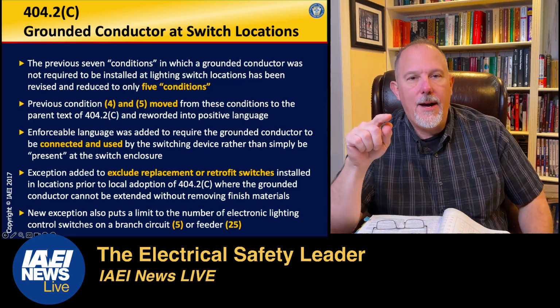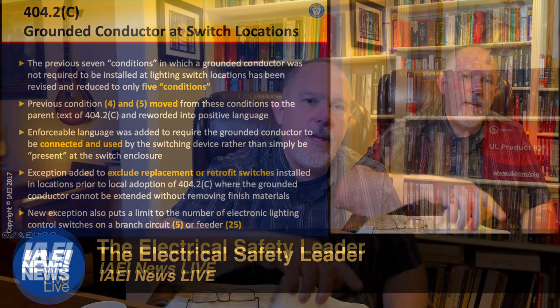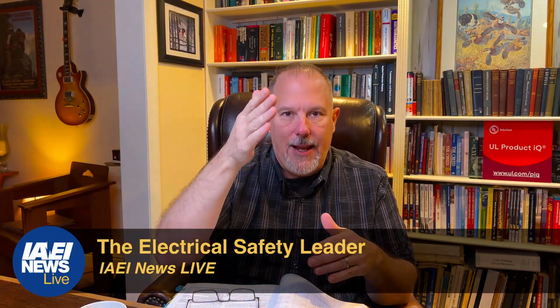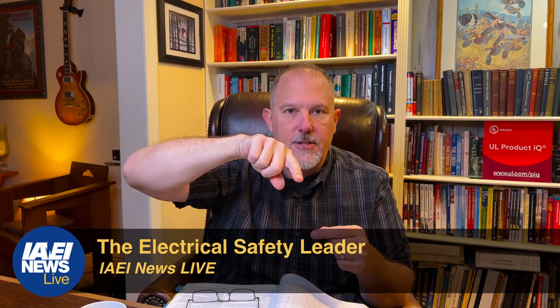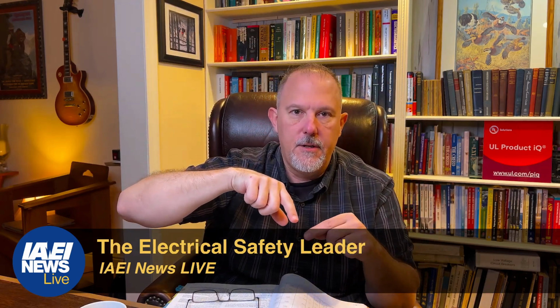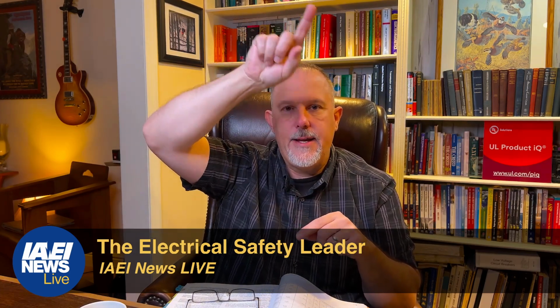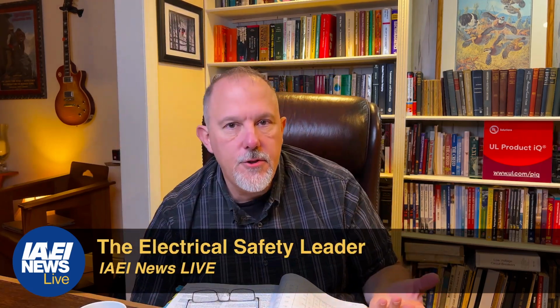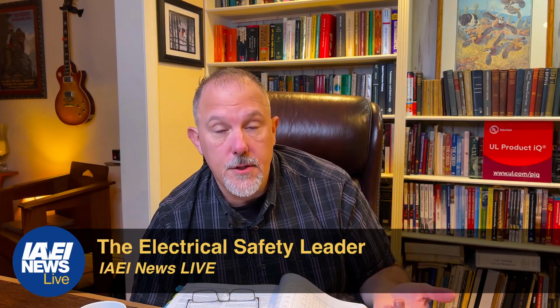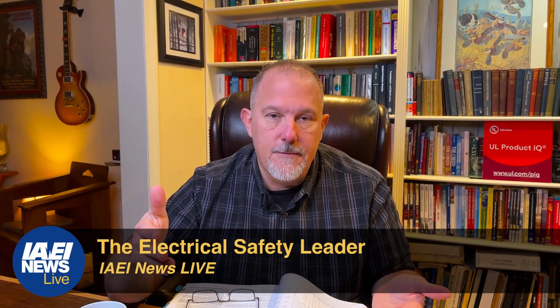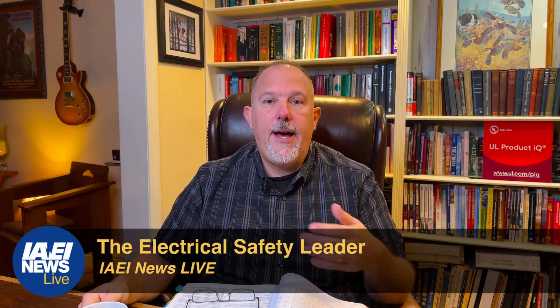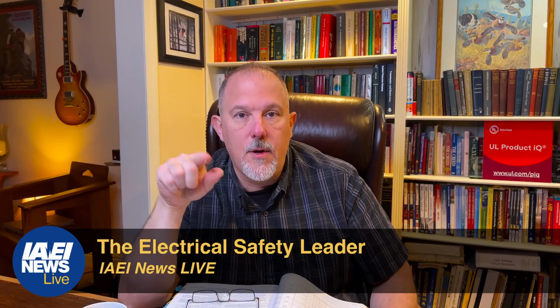You take an existing, how did we usually do switching? When we deal with lights, we put a light switch in, and we would bring down a hot conductor and an equipment grounding conductor, break that hot conductor, go back up and continue it. It's sort of a drop leg. We would drop the hot conductor down, break it, bring it back up, and go to the light. You didn't have to bring the neutral. It served no purpose because you were only switching the hot conductor. And you would bring the equipment grounding conductor. So when you opened up a light switch in a lot of these older homes, you had two conductors, which was basically one conductor that was cut, that you're breaking with the switch, and you had an equipment grounding conductor.